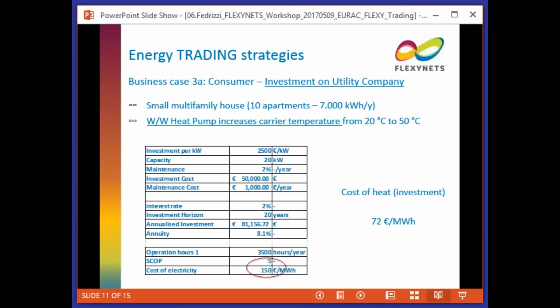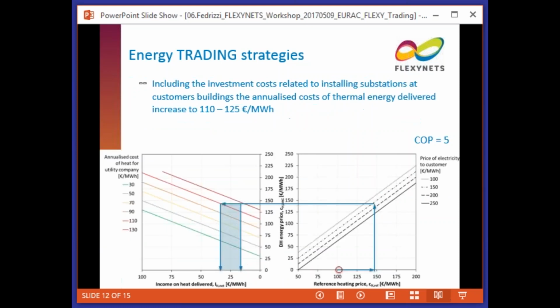And again, what we do is to raise the temperature from the network level in the range of 20 degrees up to 50 degrees for domestic hot water purposes. Again, here are some numbers: 50,000 euros the entire initial capital cost for the building, which is around 5,000 euros per dwelling, and the annualized investment in the range of 81,000 euros. Seasonal COP 5, and in this case we accounted for the final customers paying the electricity bill separately from the thermal energy taken from the network.